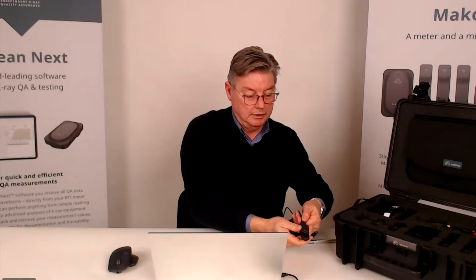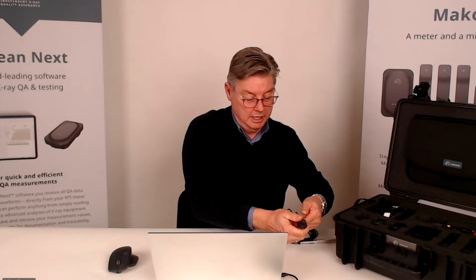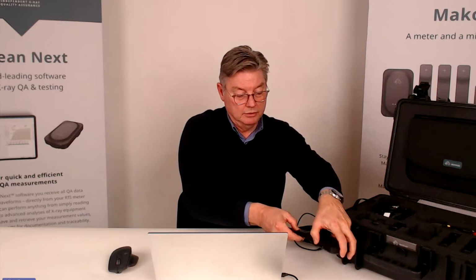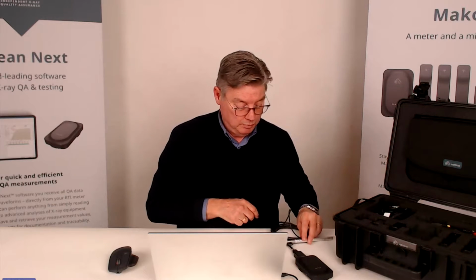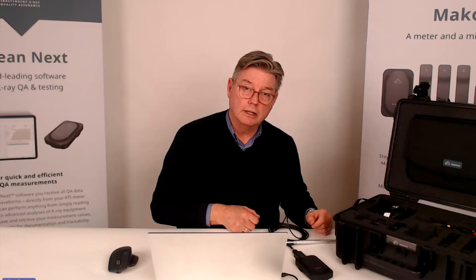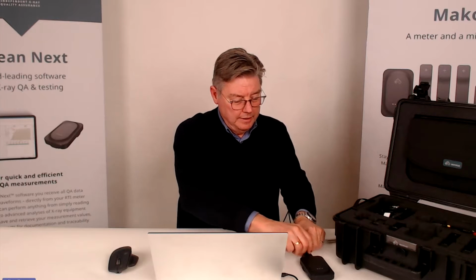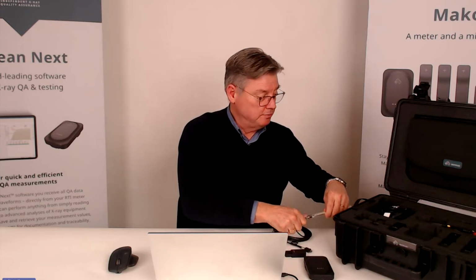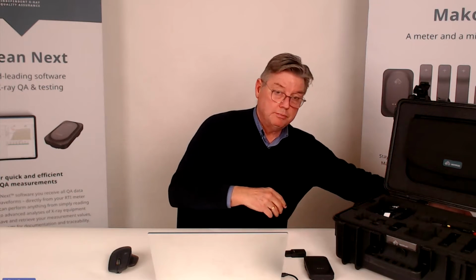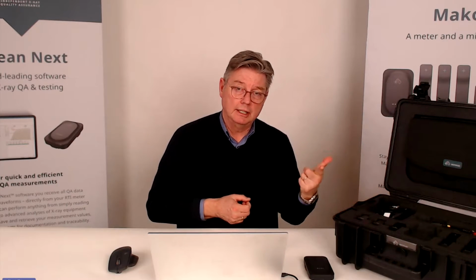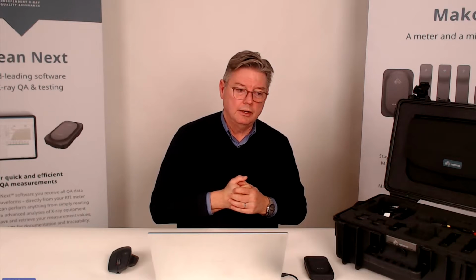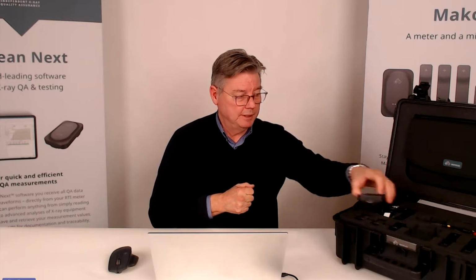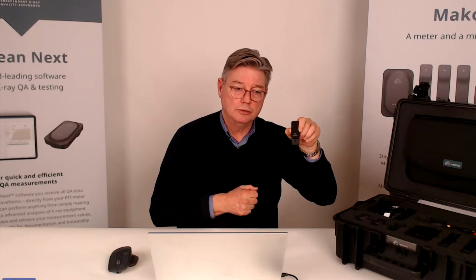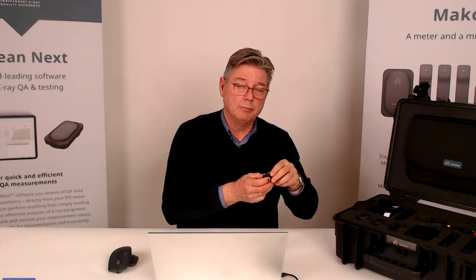The connector goes in, you hear the same double click as before, and we're connected. This, of course, then goes into the base unit like so, and we have the functionality for the CT dose profiler measurement. And this is not only for the CT dose profiler, it's for your external dose probe, RTI dose probe, the T20, the light probe. Of course, if you have a mass 1, it will also work with the legacy module, as will the existing mass 2, etc. All probes that we have for the Piranha will work, except the chamber adapter. That's why we have the ion chamber module, to have an improvement over the performance of the chamber adapter.